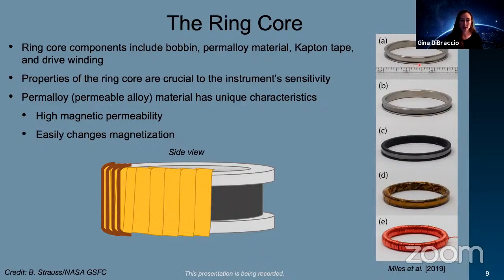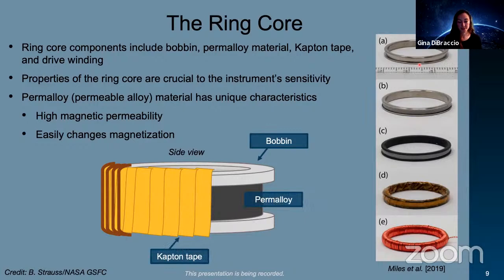Getting into more detail about the ring core components: essentially there's a bobbin that we start with for the ring core. Then we have permalloy material wrapped around the bobbin, Kapton tape that goes around that, and the ring core is finished off with a drive winding, a magnetic wire wrapped around everything. The properties of the ring core are crucial to the instrument's sensitivity, and this permalloy material is special because it has unique characteristics that enable these measurements—high magnetic permeability, but it also easily changes magnetization.